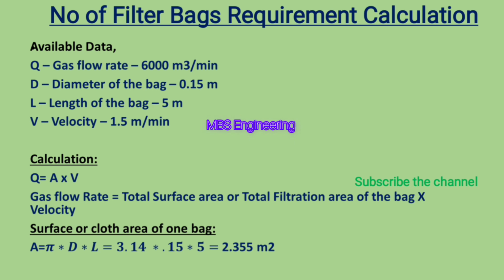A equals pi multiplied by D multiplied by L, which means as per the given data, 3.14 multiplied by 0.15 multiplied by 5 equals 2.355 square meters. Based on the above equation, we got the filtration area of one bag, 2.355 square meters.